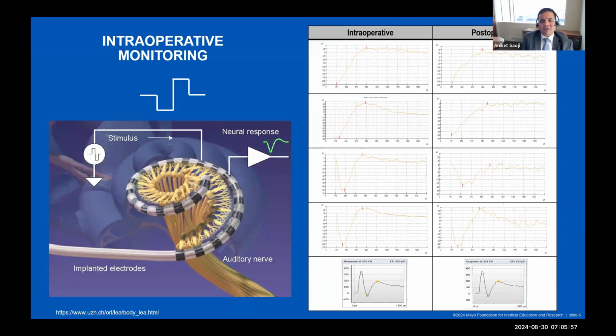Now, while using a cochlear implant, the way this is measured is we present a single biphasic pulse on, let's say, one of the electrodes, and then we use an electrode a couple of electrodes away in the cochlea to record that potential. So the stimulus is presented inside the cochlea and the recording is made inside the cochlea. This is typically measured through the cochlear implant.